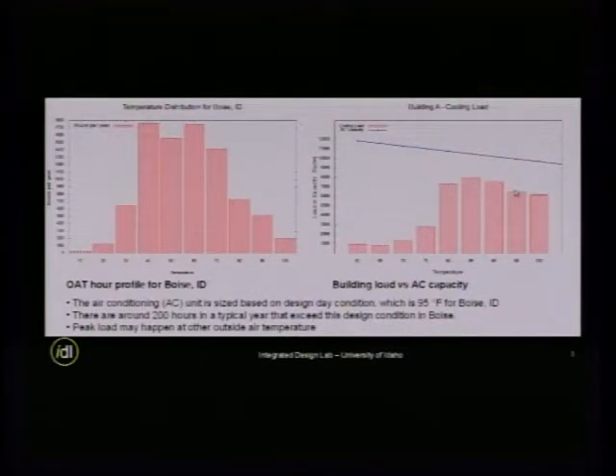So to make it even more complicated, this line here is the air conditioning capacity. Air conditioning capacity depends very much on the outside air temperature at the condensing unit. So as the air temperature goes down, the air conditioning capacity actually goes up. So you can see that most of the time we will have this condition, right?